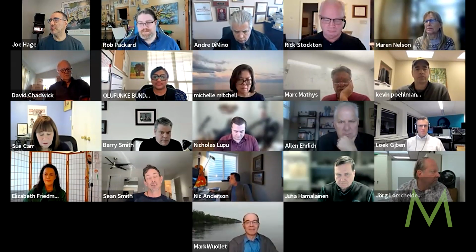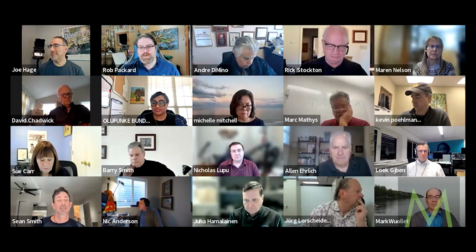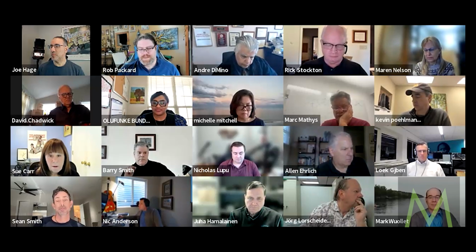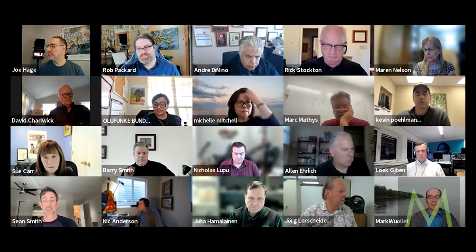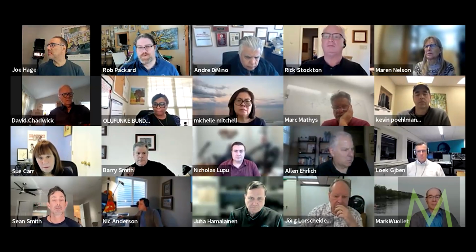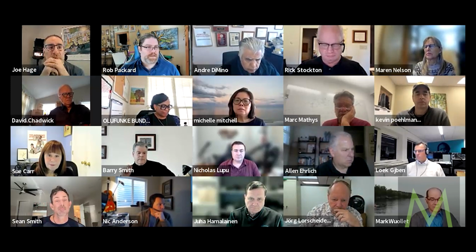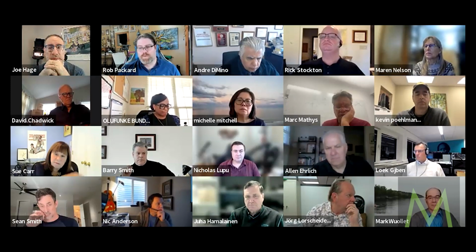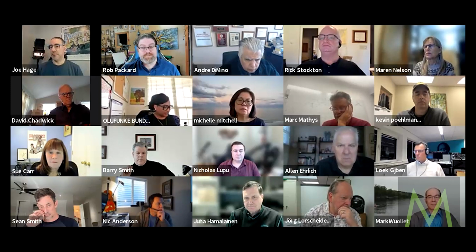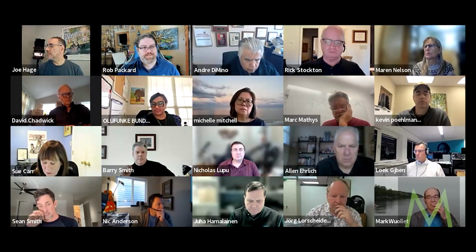It's going to be released later than anybody is guessing. Mary Votter is one of my employees. She was actually hired by AAMI to rewrite the compendium document. Now the FDA is going to be co-writing it with AAMI's consultants, and they are going to be making a bunch of modifications for what's going to be the new QSR. So that's totally different. I would say that the FDA is not going to require certification for anybody, they've already said they won't. So it's voluntary, but you will have to comply with 13485. But we will see that announcement come soon, but it's not out yet.